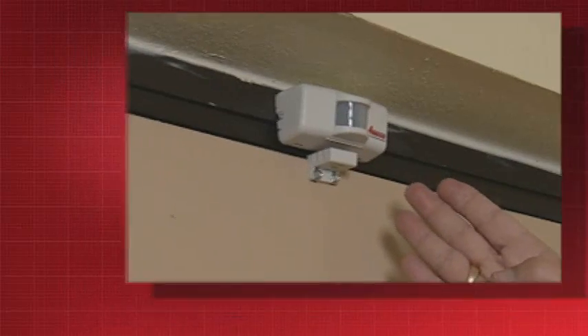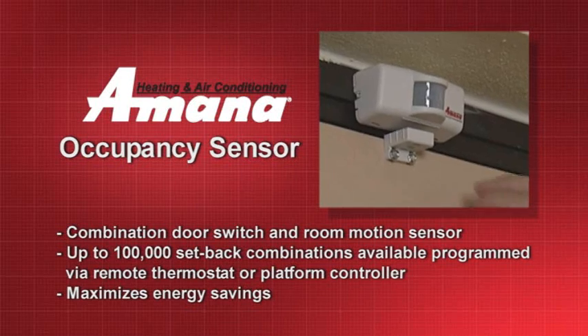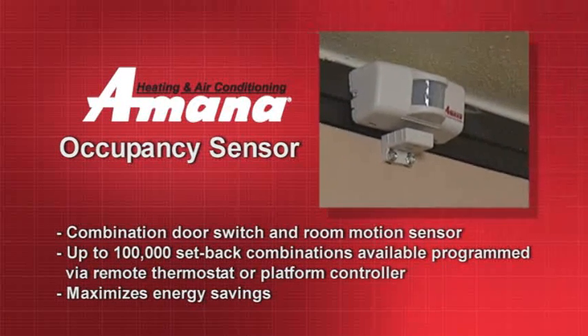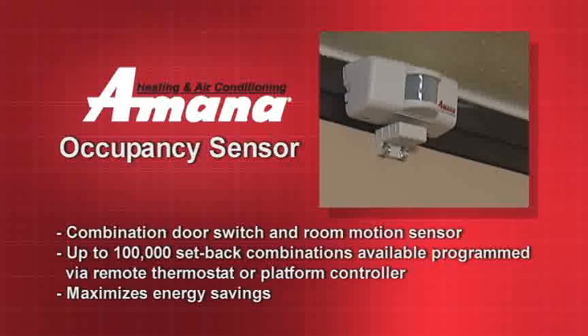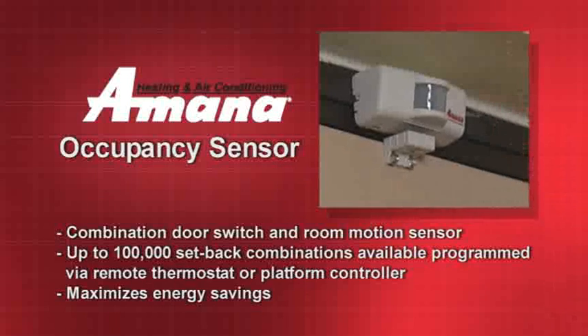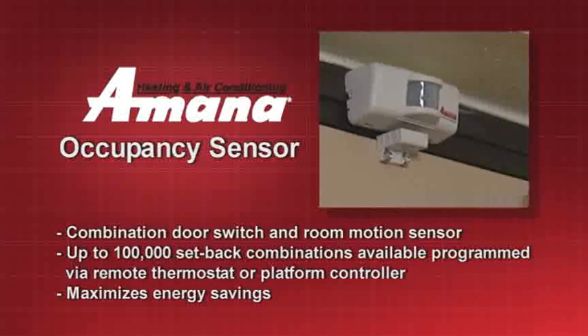This is the Amana DigiSmart occupancy sensor. It's actually a dual function device. We have a magnetic switch on the bottom. When the door is closed, we know that the door is closed because the magnet is actually closing a switch in the bottom of the device. And when the door opens and closes, then we're able to know that we've had a door event that allows us or triggers us to look for motion.